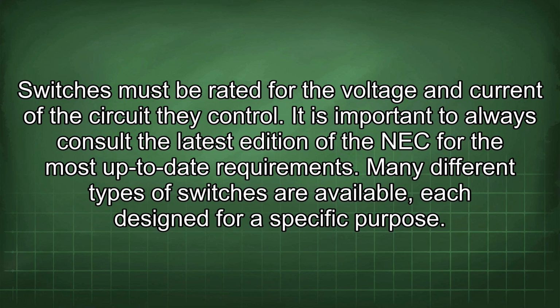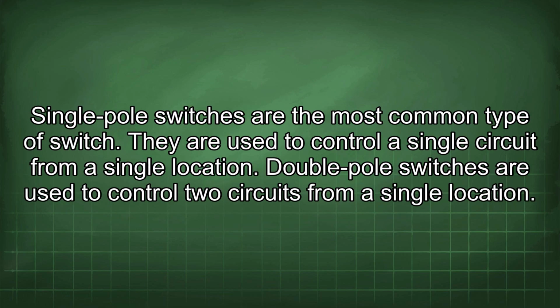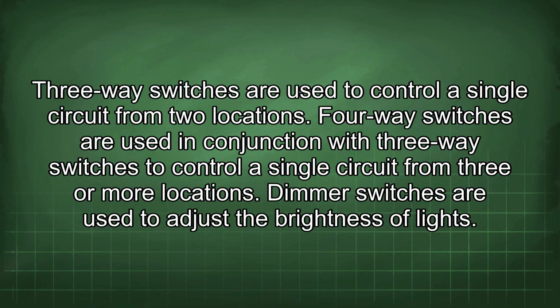Many different types of switches are available, each designed for a specific purpose. Single-pole switches are the most common type of switch. They are used to control a single circuit from a single location. Double-pole switches are used to control two circuits from a single location. Three-way switches are used to control a single circuit from two locations. Four-way switches are used in conjunction with three-way switches to control a single circuit from three or more locations.